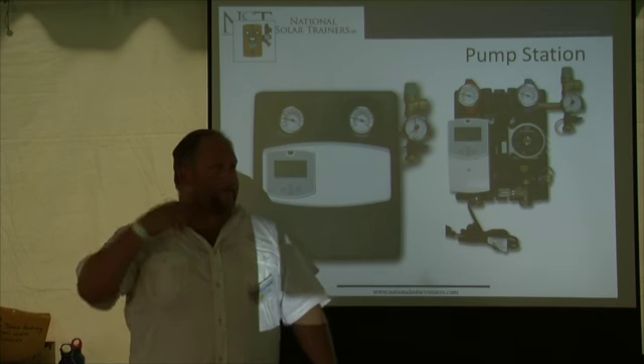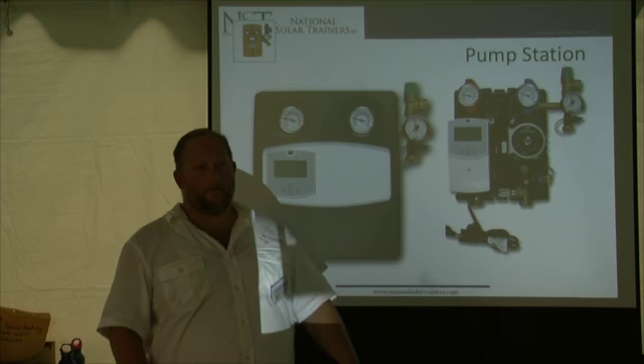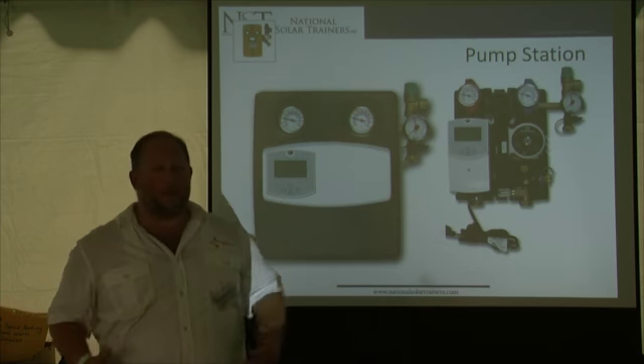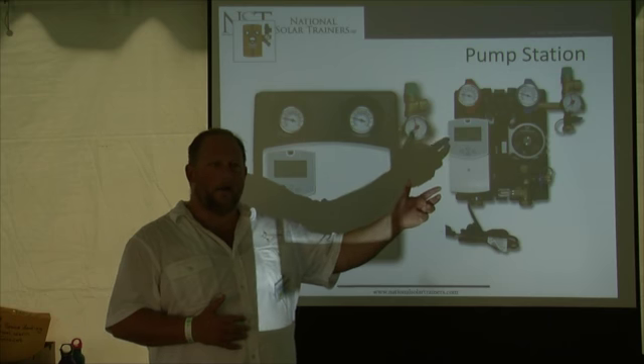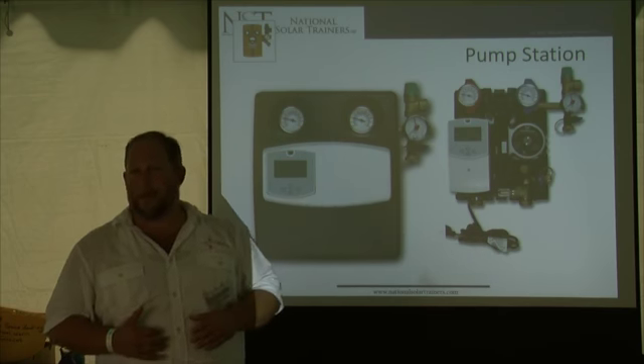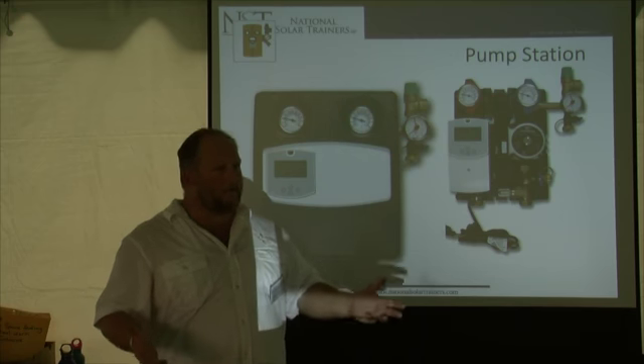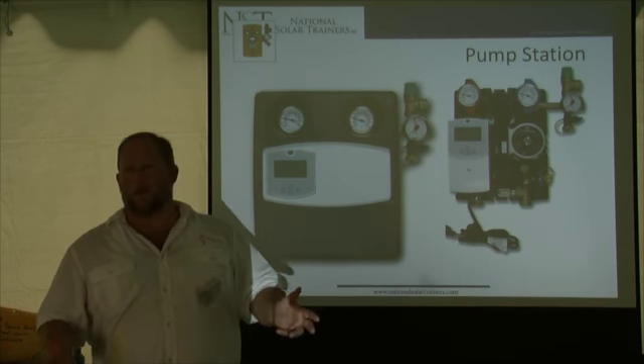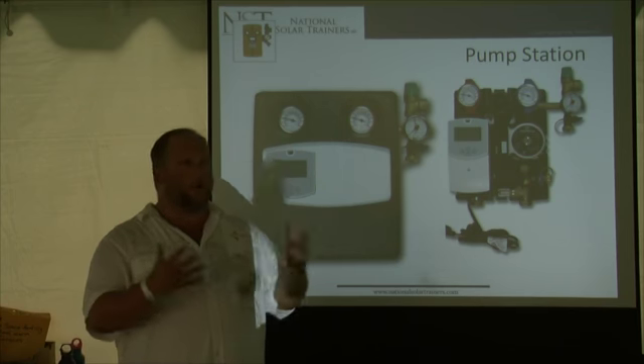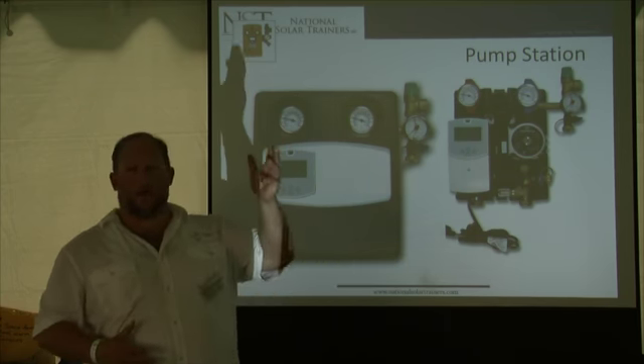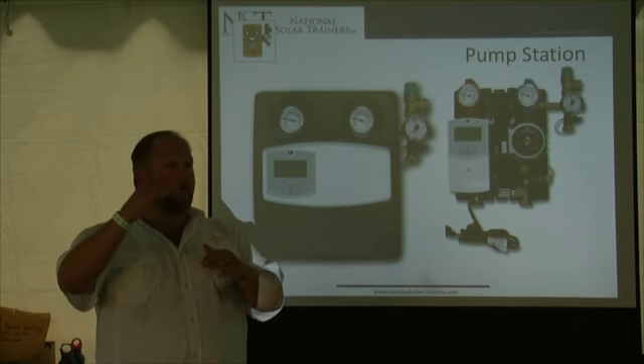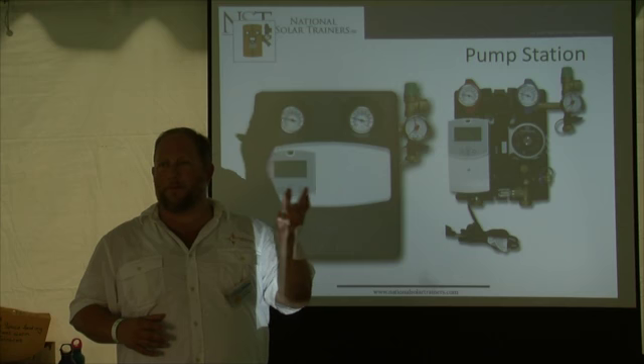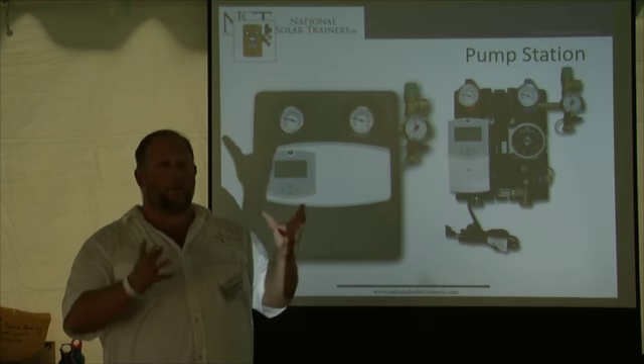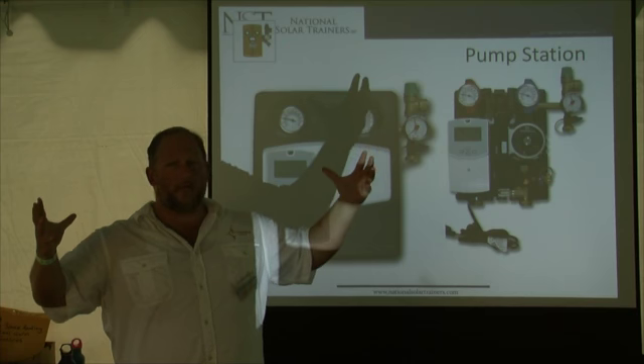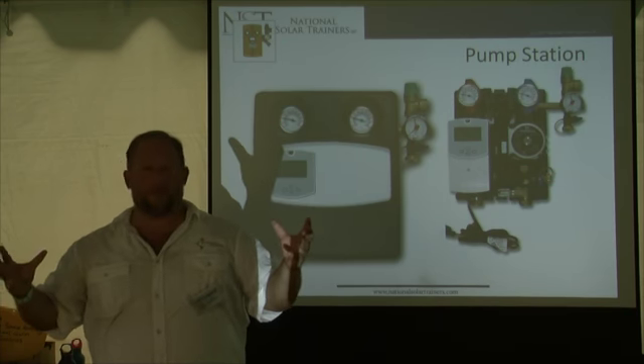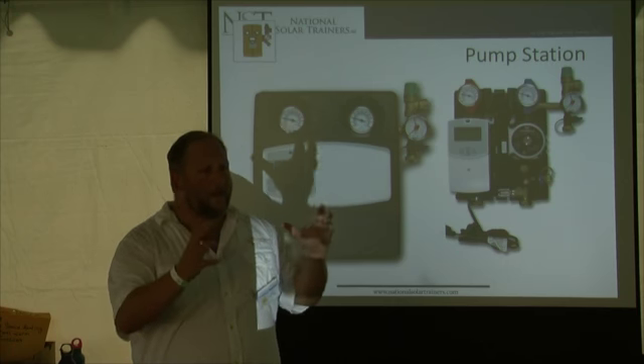All right? So how do we prevent the glycol from overheating? Well, the glycol can't be in the collectors when the collectors are that hot. Well, how do we empty the collectors when they're that hot? We don't. We let the laws of physics do that for us. Boyle's law: when the temperature of the glycol increases to a point where the boiling point has been met, the water boils first. The water creates steam, increases the volume by 1,000%, and increases the pressure inside the collectors.